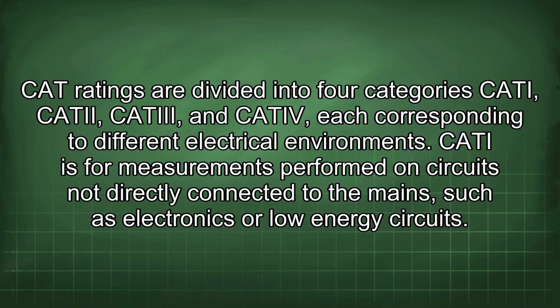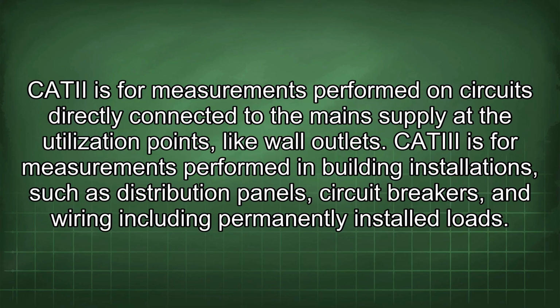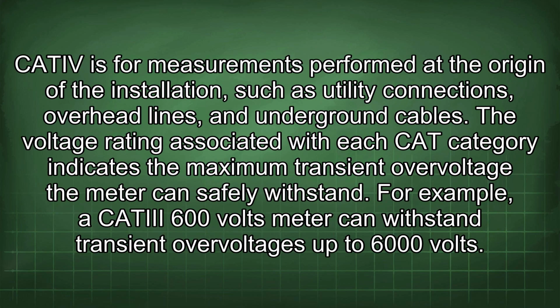CAT I is for measurements performed on circuits not directly connected to the mains, such as electronics or low-energy circuits. CAT II is for measurements performed on circuits directly connected to the mains supply at the utilization point, like wall outlets. CAT III is for measurements performed in building installations, such as distribution panels, circuit breakers, and wiring, including permanently installed loads. CAT IV is for measurements performed at the origin of the installation, such as utility connections, overhead lines, and underground cables.